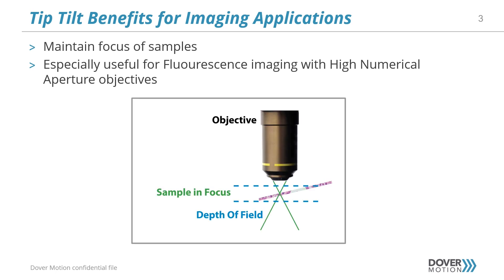This is usually needed for applications that have a high numerical aperture or high magnification objective. In this example you can see that the sample is angled. This is exaggerated for demonstration, but angular errors can come from the surface of the slide or from flatness variations in the motion axis.